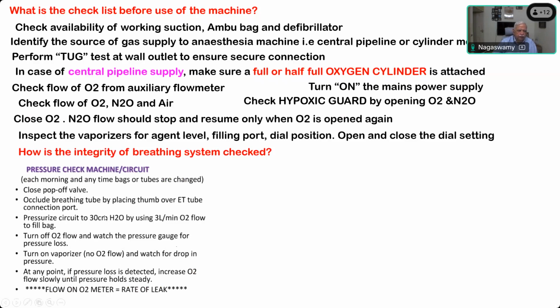But the pressure remains 30 centimeters. But once you open the vaporizer, if the pressure starts dropping in the pressure gauge, that means there is a leak in the vaporizer attachment, especially with the removable interlocking system of vaporizers. This can be a common problem. There may be a leak at the part where you fix the vaporizer. So you have to individually test for the leak at the flow meter level and at the vaporizer level, and that can be done only by watching the pressure in the airway pressure gauge.